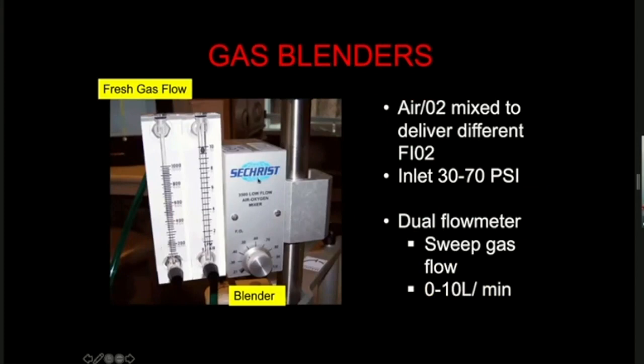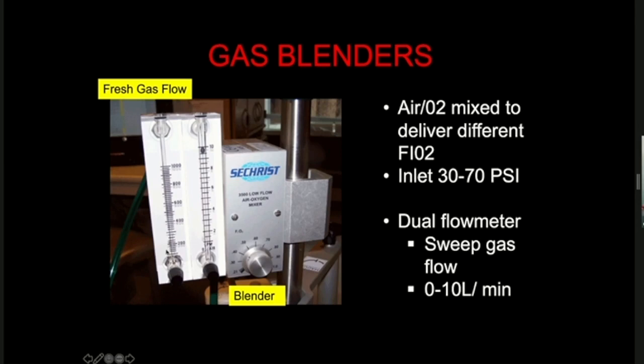The next component is the gas blender, which is connected to the wall panel medical gas supply as well as the oxygen supply. The blender allows you to titrate the concentration of oxygen supplied. For VV mode, we typically set it at an FiO2 of 1.0, and even during the weaning process, we usually don't titrate this level. The flow meter column can go up to 10 liters per minute of sweep gas flow, or as low as millilitres, which is used for neonatal support or for extreme weaning.